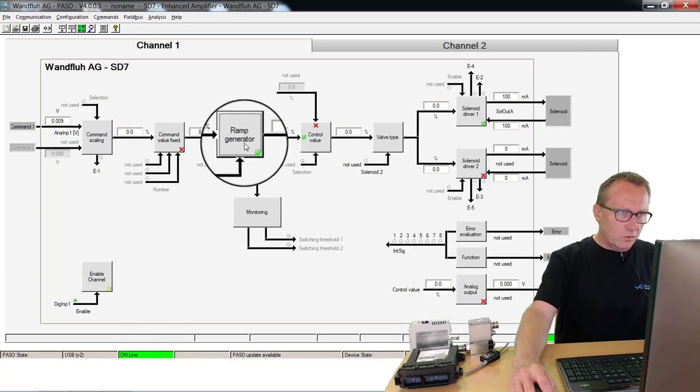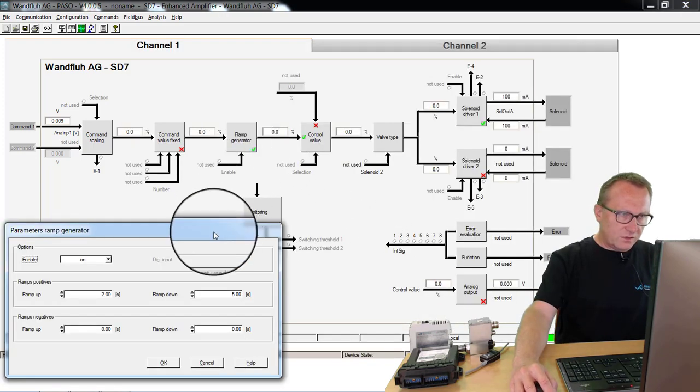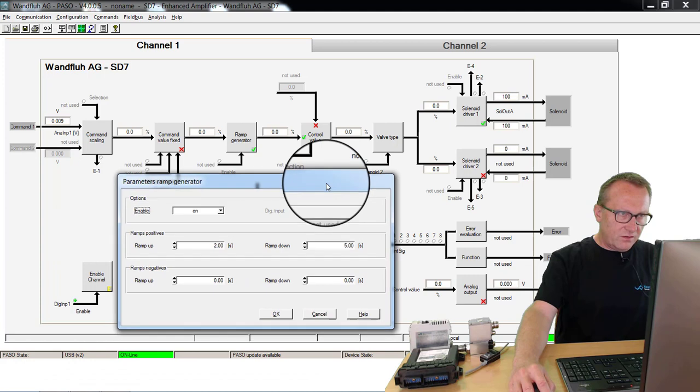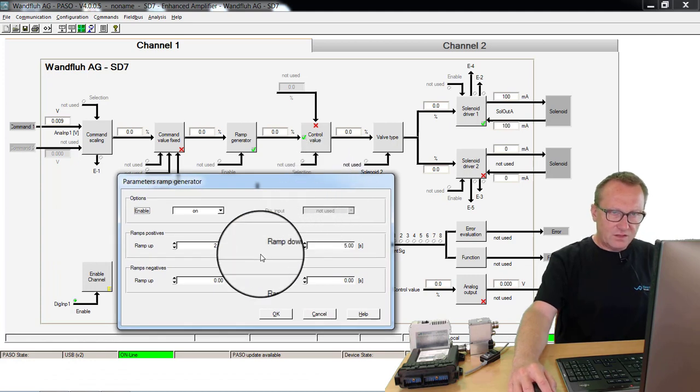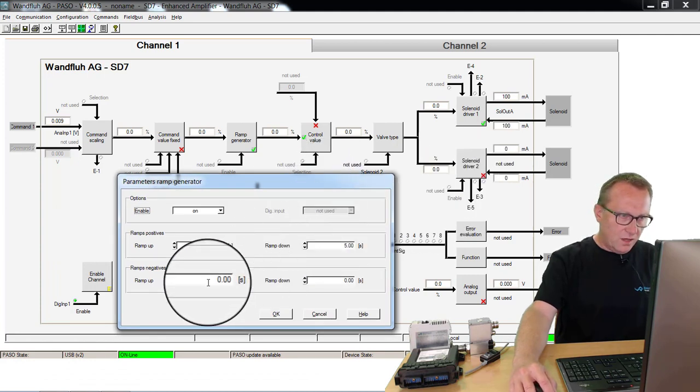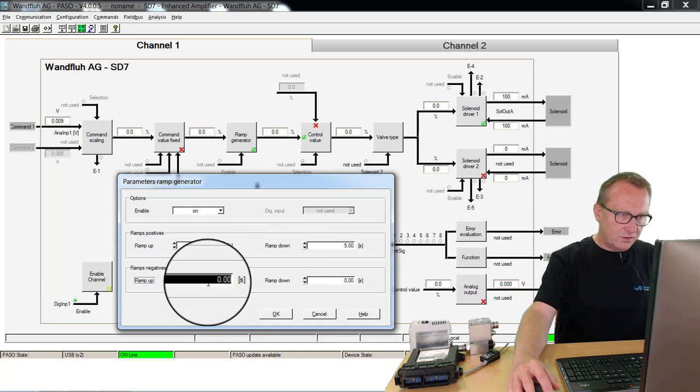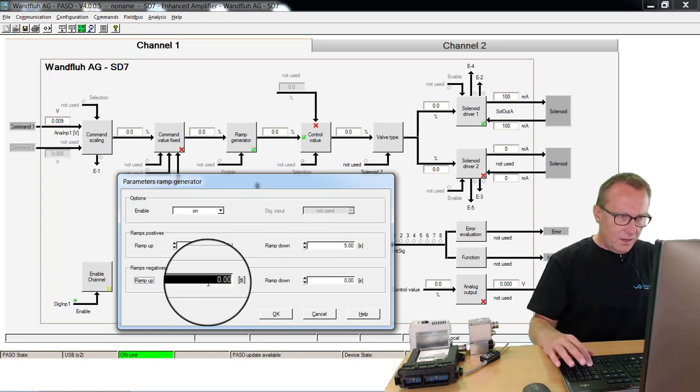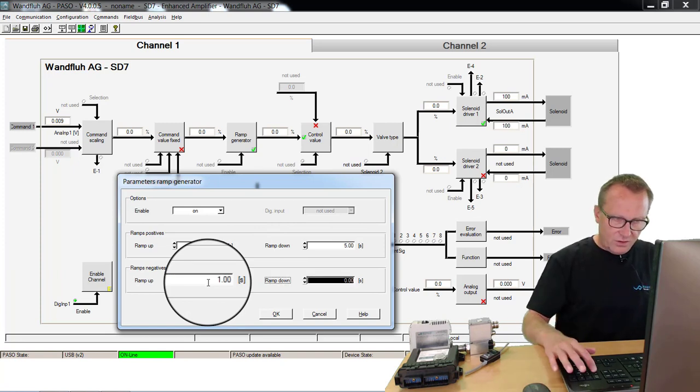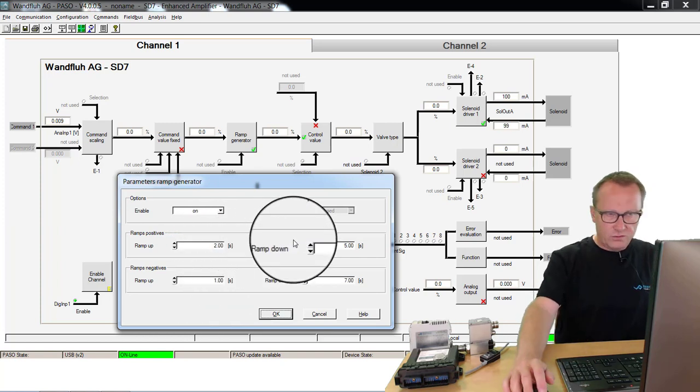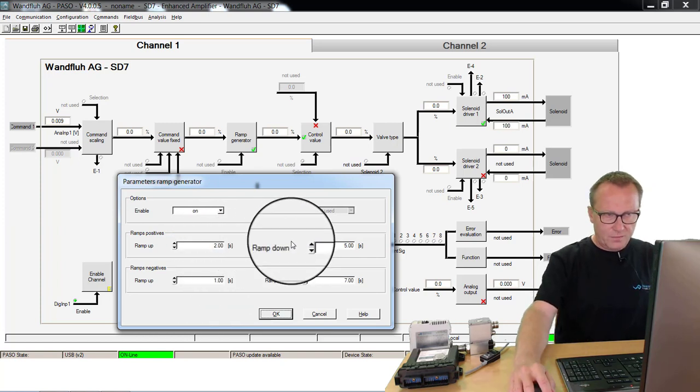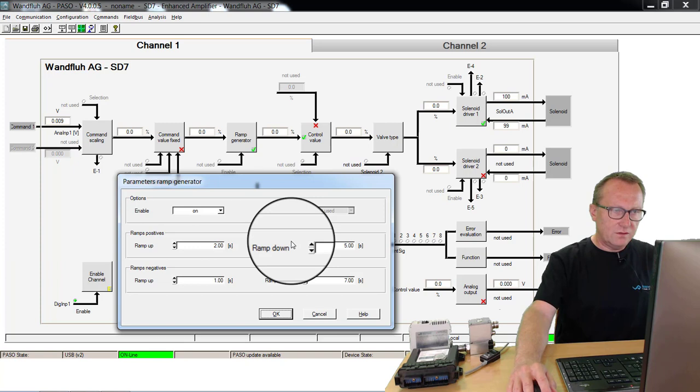You can do more adjustments inside this ramp generator. For example, if I have a second solenoid output, I can adjust also here a ramp, and these values for this ramp can be different to the values from the first ramp. Must not be the same values.